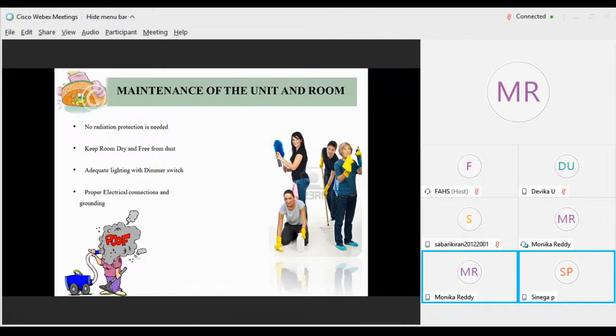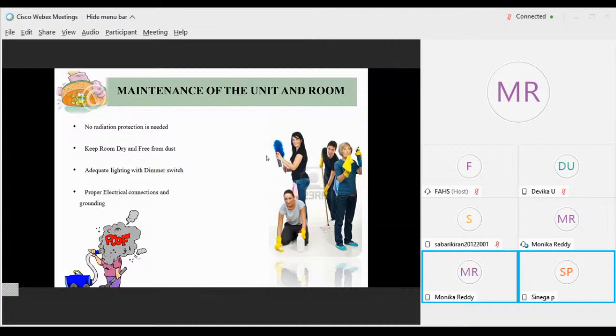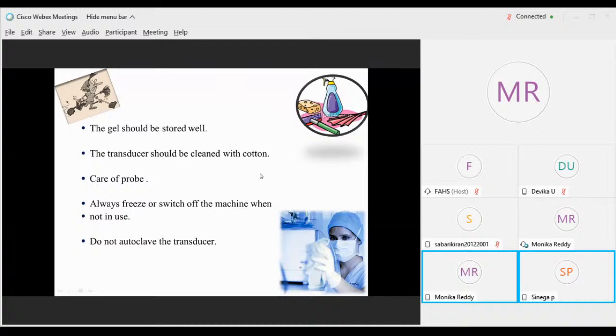We have to follow up on these electrical connections. So is the grounding proper or not, are there any wire damages or transducer damages. These things we should note regularly. And the gel should be stored well, and the transducer should be cleaned with cotton. We are not supposed to use any solutions on the transducer for cleaning. We should use just dry cotton to clean, and we should care for the probe.